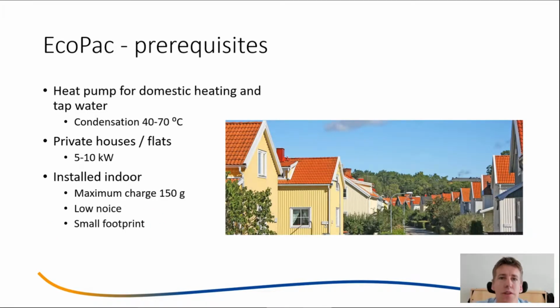So the prerequisite: when should we use EcoPac or a solution like EcoPac? What we are aiming for is to build a heat pump for domestic heating and tap water heating. That means we will have a condensation temperature around 40 to 70 degrees. In this project, we are looking at a smaller application, meaning private houses or bigger flats, somewhere in the range of 5 to 10 kilowatt.